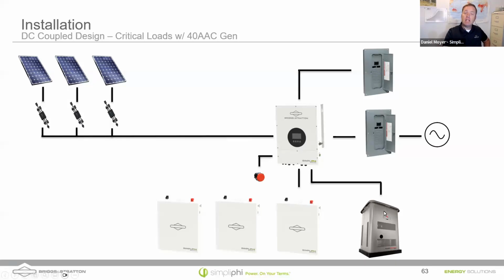The generator can be started and stopped based on what the inverter sees. The inverter has a 2-wire signal to start. We can signal the generator to start usually based on 2 factors. One, if the state of charge of the batteries is getting too low, and it's cloudy out or nighttime, we can use the generator to charge up that battery bank and then shut it off. We could also use the generator to help support large loads that the inverter couldn't otherwise handle.